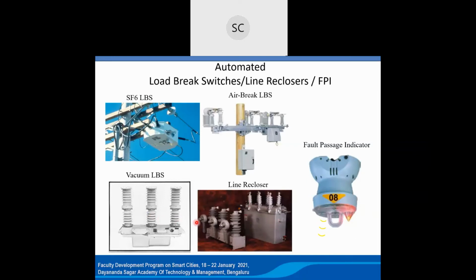The sectionalizer is nothing but a simple load break switch. It cannot handle fault current. During the fault time, it gets tripped. Once it has tripped and the fault is still there, it cannot switch on. So what we will do through the control center is automated switching with the operator support. When the fault is removed, the operator from remote control will switch on these switches when it comes to normal. That is how it happens. So temporarily, reconfiguration of the feeder is possible by this philosophy.